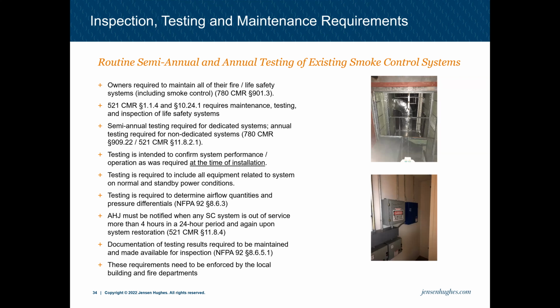A couple of quick things we will talk about are the ongoing items, just to ensure that you are all aware of them. Primarily that would be routine, semi-annual, and annual testing of existing smoke control systems. If you have dedicated smoke control equipment, such as dedicated stair pressurization fans or elevator pressurization fans, those must be tested every 6 months. And if you have shared equipment, such as an exhaust fan for an atrium that also serves HVAC purposes, that must be tested for smoke control annually.